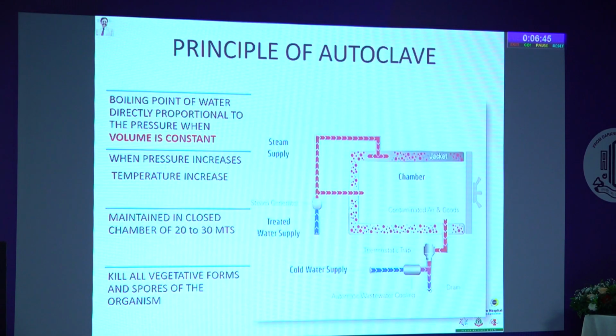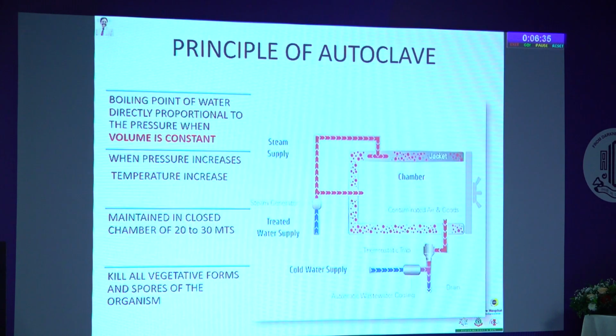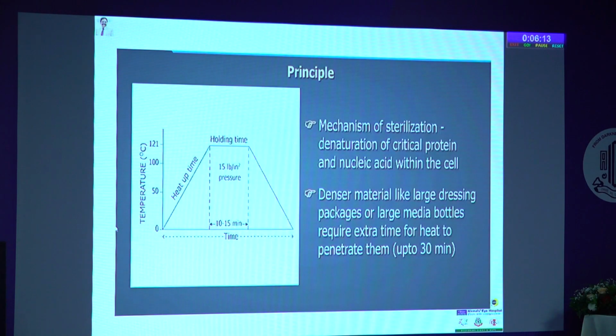So this is the principle. Water, when boiled to its boiling point, and when the pressure is raised with the volume constant, steam is produced. And when the closed chamber pressure rises, it kills all vegetative forms and spores in the instrument or the bundle we have loaded into the autoclave. So this is the simple principle, and most autoclaves work on this principle. There are certain control mechanisms.